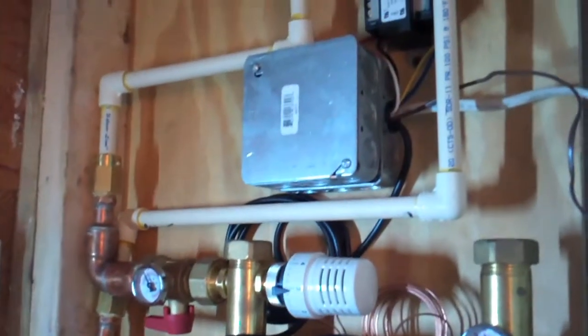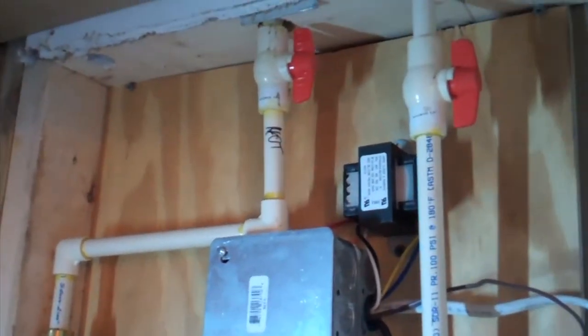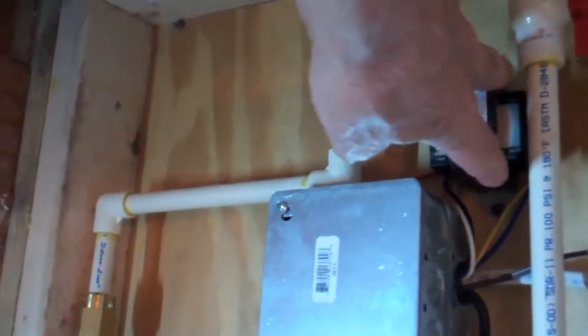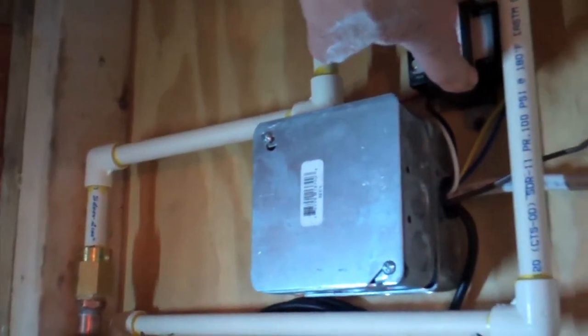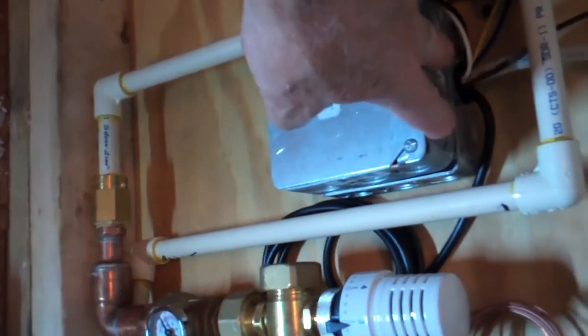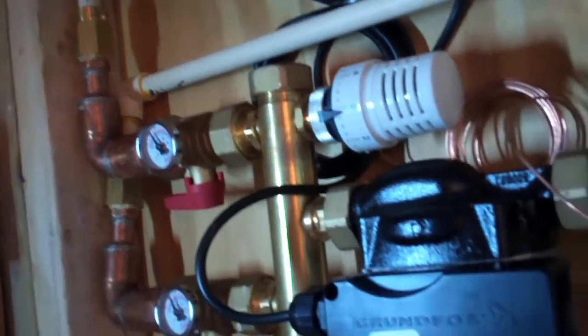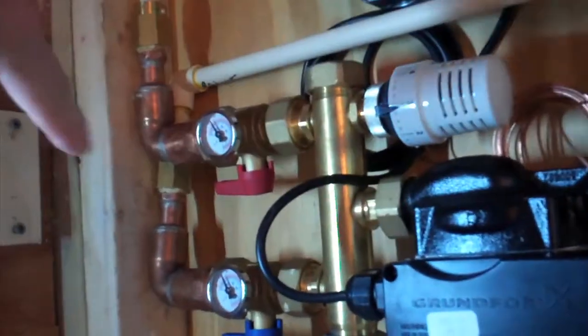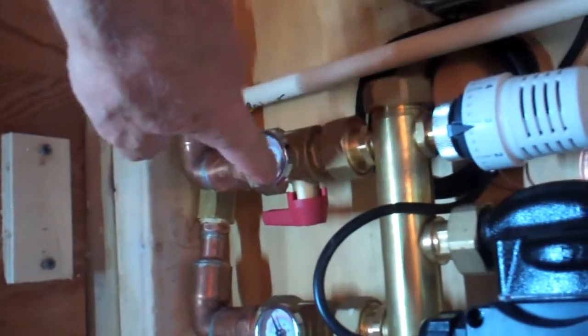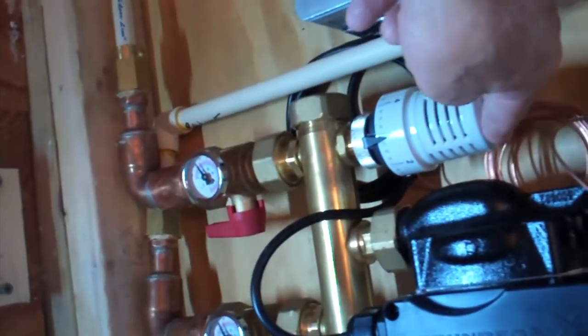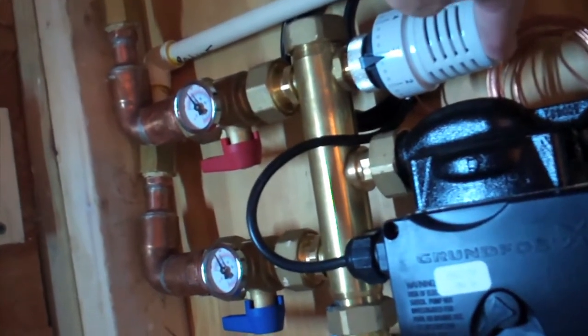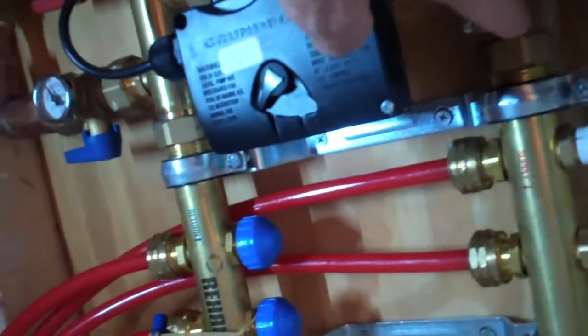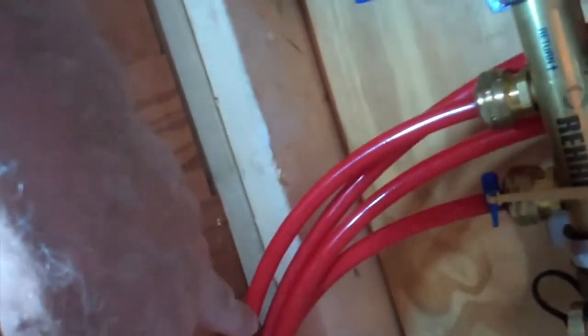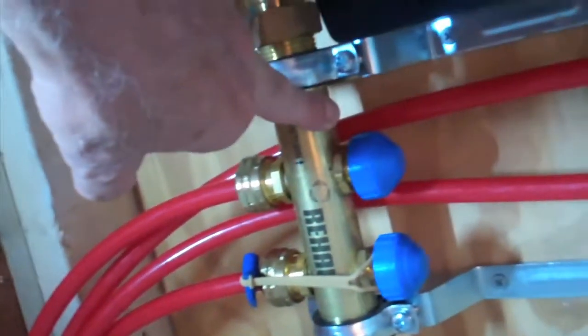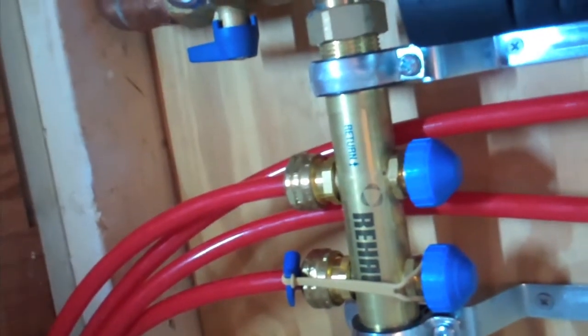Okay, we're looking at the controls for the radiant system. There's a thermostat on the wall. You've all seen thermostats. That is connected to a DC transformer, which turns on an AC switch that powers our pump. The hot water comes up from the tank into the manifold here. We have a temperature setting which adjusts the temperature going to the floor. The pump delivers it to the floor, and then it goes out through these red pipes into the floor, and it returns through another set of red pipes into the manifold here, and then back to the tank again.